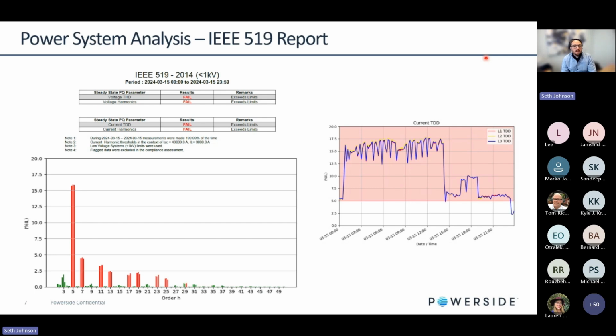Now, 519 compliance is a compliance standard at the point of common coupling, so it's where the utility and the customer connections basically meet, and it's looking at both total demand distortion as well as total harmonic distortion for voltage. So I won't go into the details of IEEE 519, but this is a real case scenario that we looked at for a client in the oil and gas space where they were exceeding their IEEE 519 compliance for both total demand distortion as well as voltage harmonic distortion all the way through.